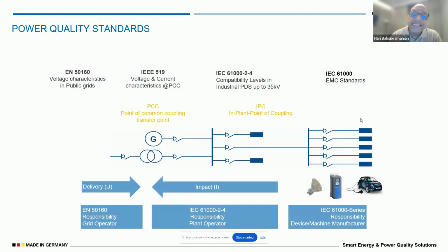And then when it comes to the PCC level, where the consumer is taking power into his system, called the point of common coupling, standards like IEEE 519 are applied. And at the compatibility level of the equipment, you have IEC 61000-2-4. So these are all the power quality limits. EN 50160 talks about voltage frequencies and so on. IEEE 519 talks about current harmonics and voltage harmonics. IEC 61000-2-4 talks about the equipment-level harmonic emissions which can be possible.